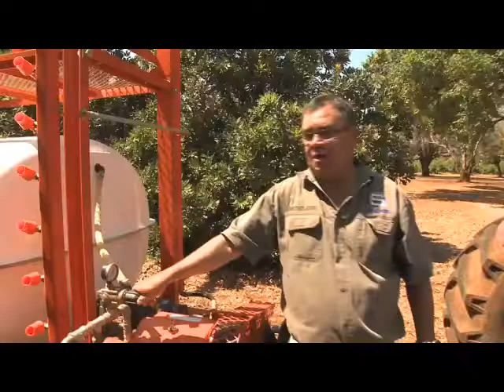It's very important to know that this was only one gun. If you use 2 guns, 3 guns or 4 guns, you need to do this all over again. Because then what happens is that as soon as you open your second gun, the pressure will drop again, and then your margin of around about 10% will go out.